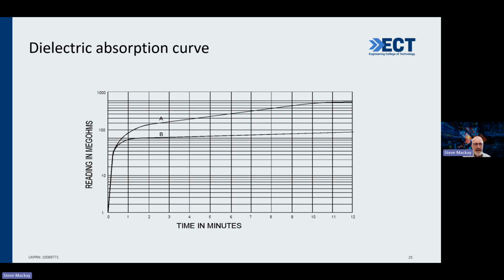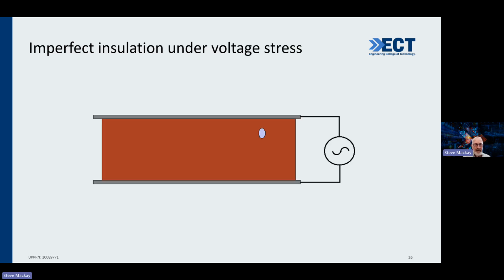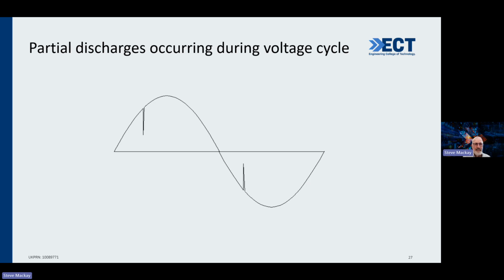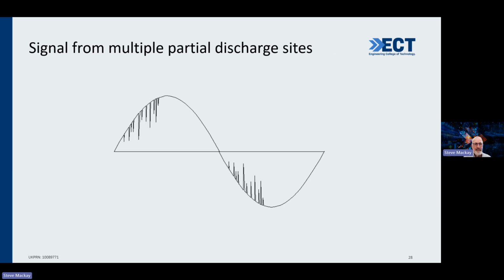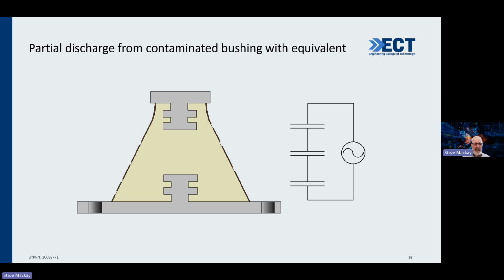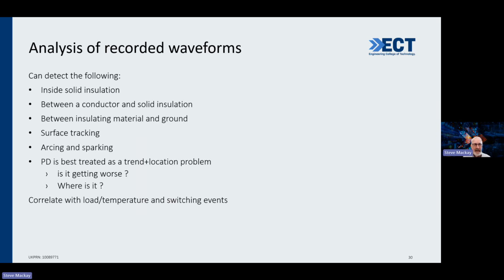And then you have a dielectric absorption curve, with imperfect insulation and partial discharges occurring during the voltage. Here we have a partial discharge from a contaminated bushing with the equivalent circuit there. Don't worry about that. Analysis of the recorded waveforms is important. You can detect the following: inside solid insulation, between the conductor and the solid insulation, surface tracking, arcing and sparking. And partial discharge is about trend and locating the problem.